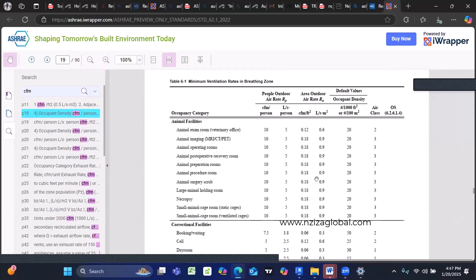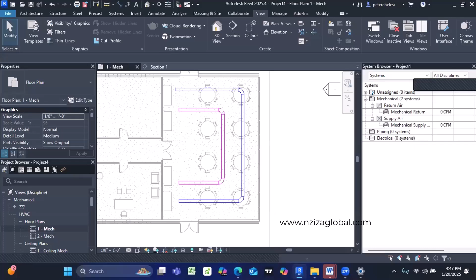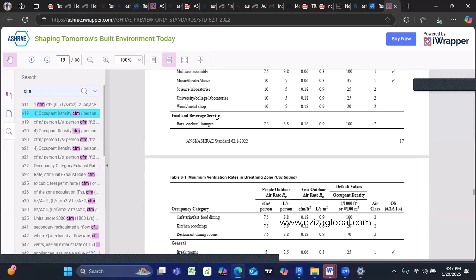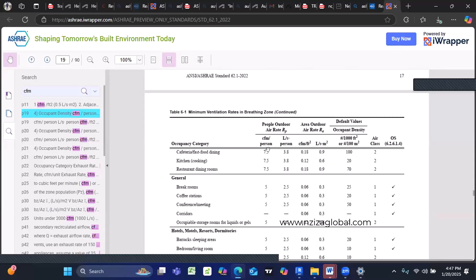So we come back to Revit. This portion, as you remember, is the cafeteria. So when you look here under food and beverage services, you can see for the cafeteria the required CFM per person is 7.5. So one person, according to ASHRAE 62.1, in a cafeteria area will require 7.5 CFM.